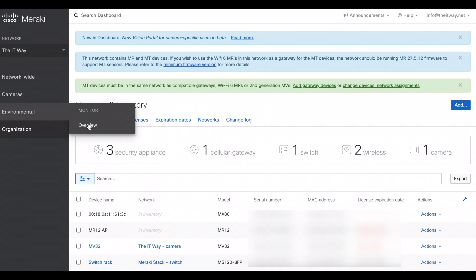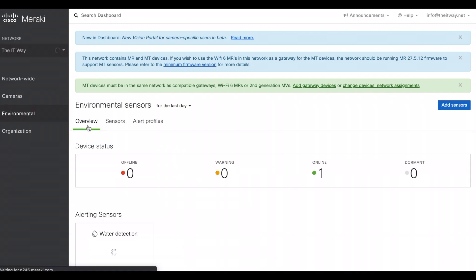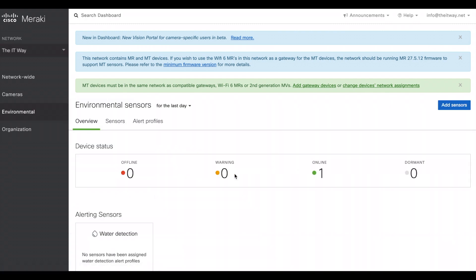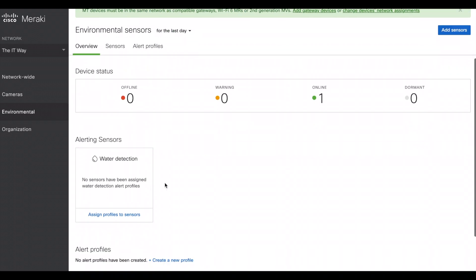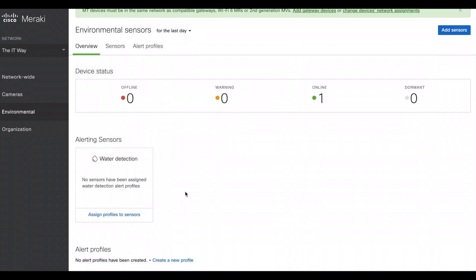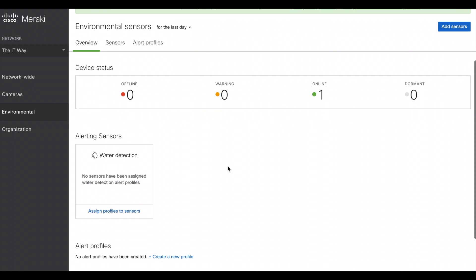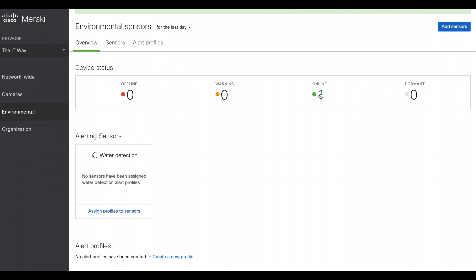If we go to environmental overview, this is the overview of this page. You're gonna have the device status to know which one is online, which one is offline, which is warning and which one is dormant. Since this is a water leak detection, that's why you have already the alerting sensor here. So we don't have any specific profiles yet because we just added that device. Here we can see that the device is already online.